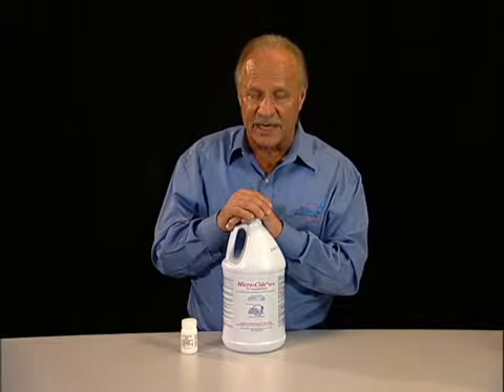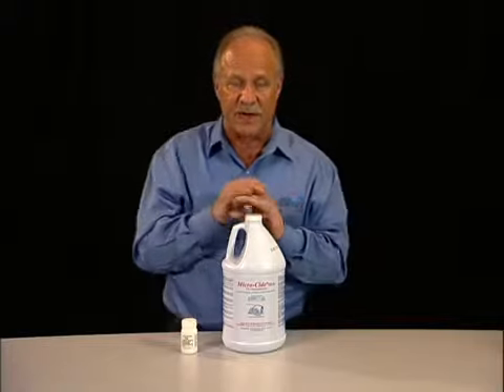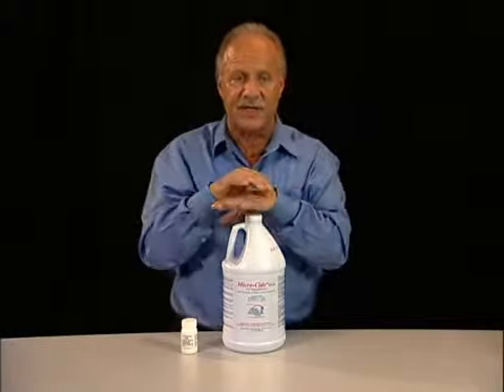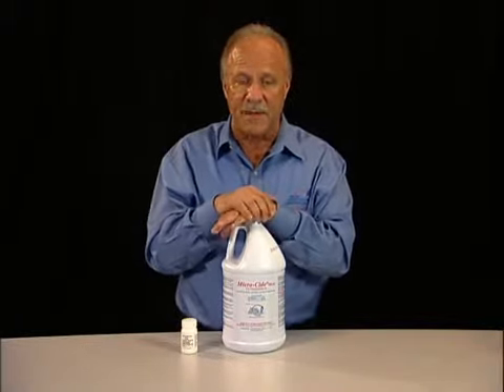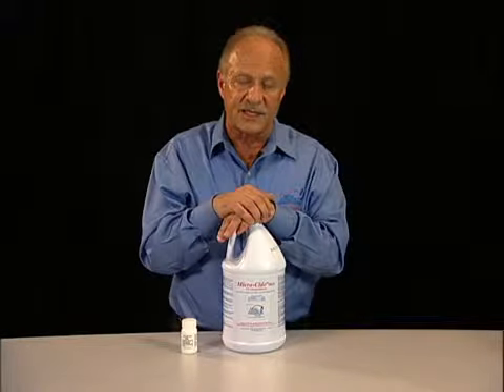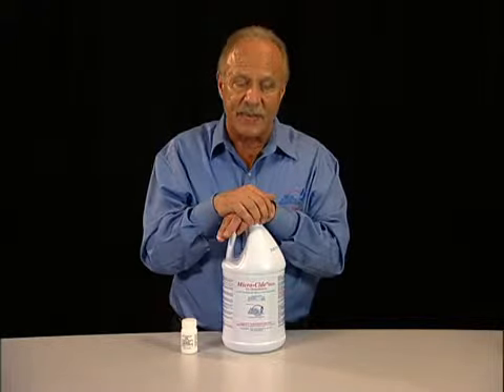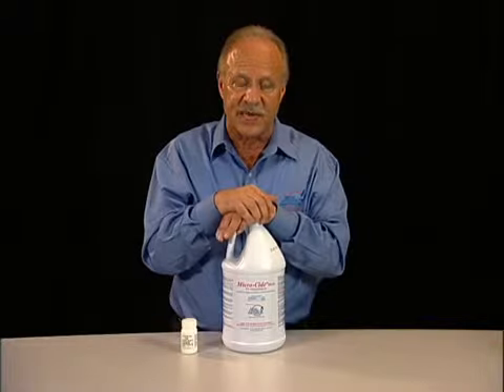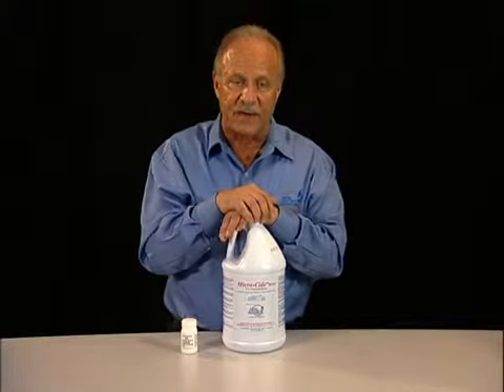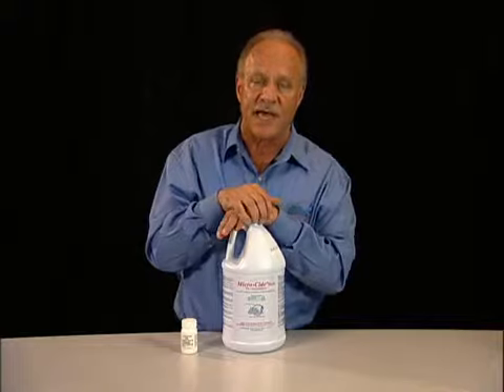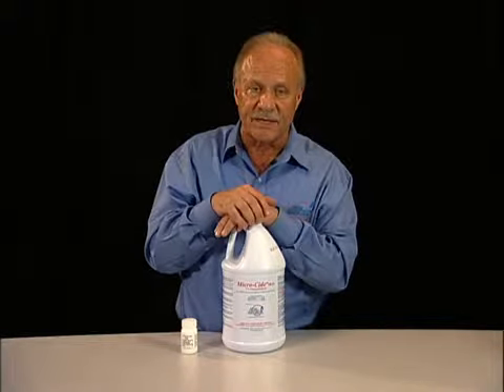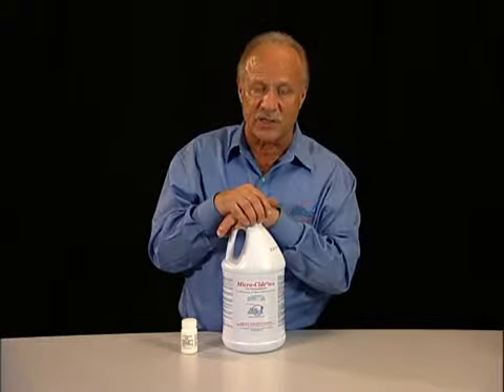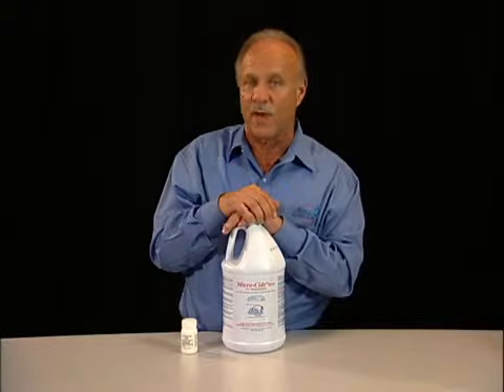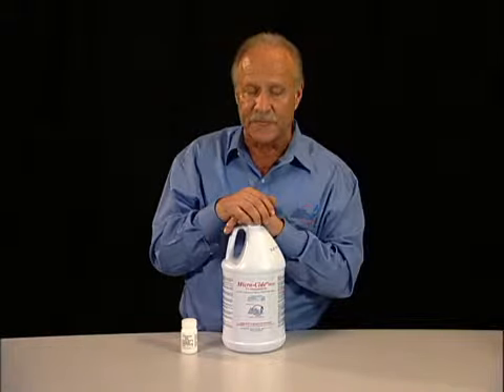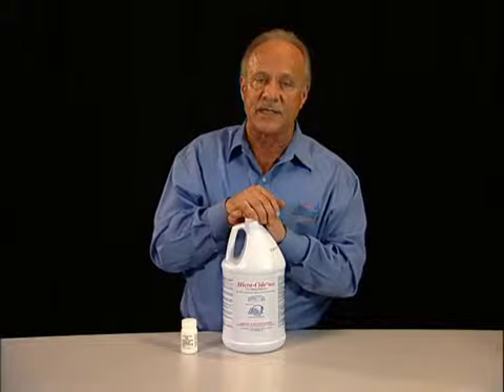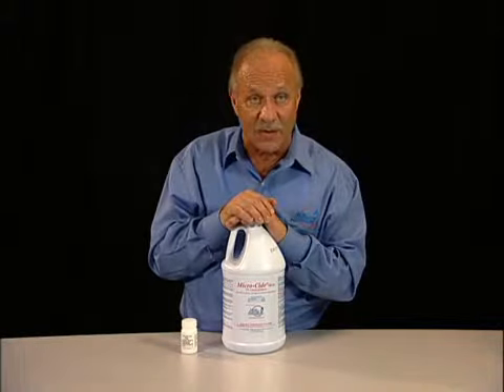There are some significant differences between those 2 products, and before I talk about this one, let me just tell you the difference between the 2 and cut to the bottom line. The Johnson & Johnson 28-day product, that's the Advanced Sterilization product, requires a 90-minute soak time of flexible endoscopes and related instruments prior to removal in order to accomplish high-level disinfection. Their 14-day product requires a 45-minute soak time.